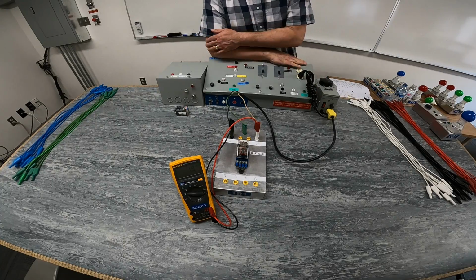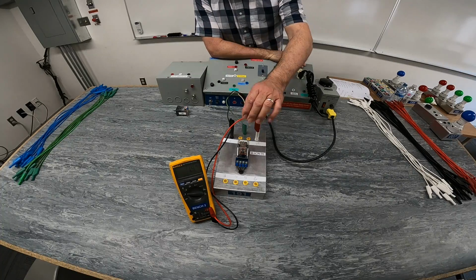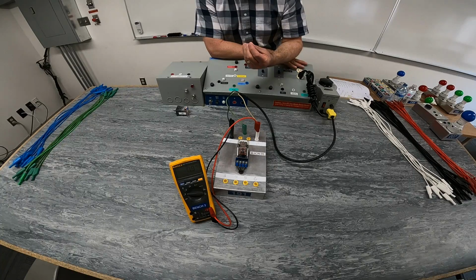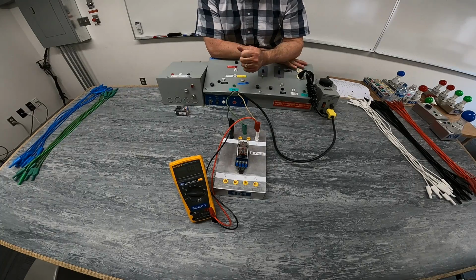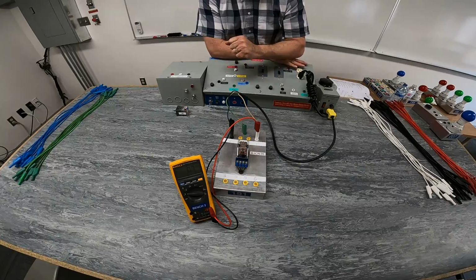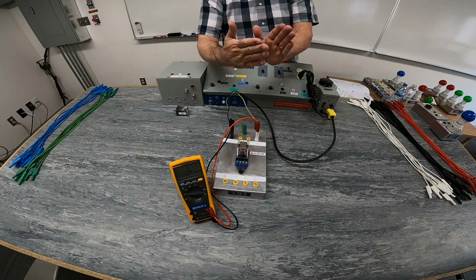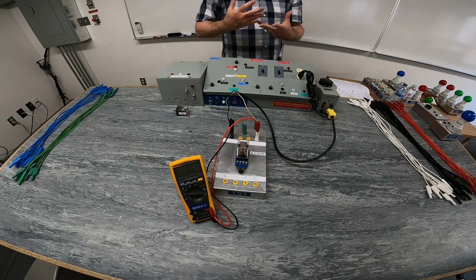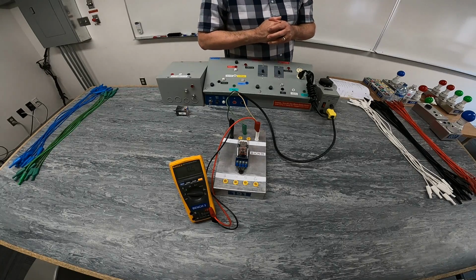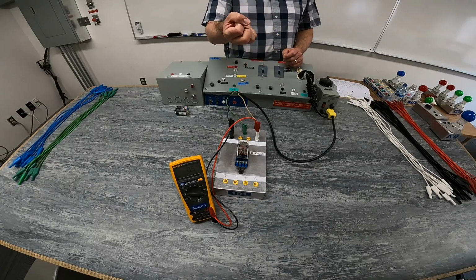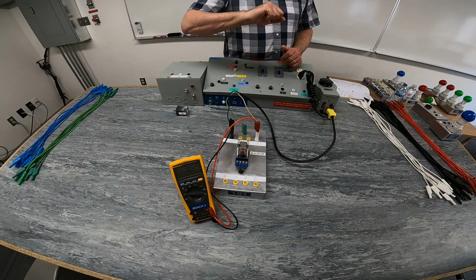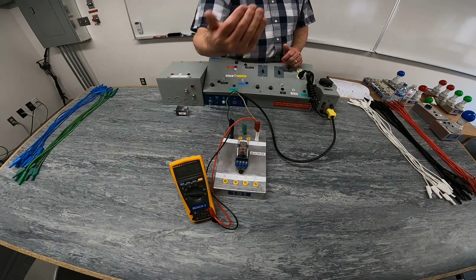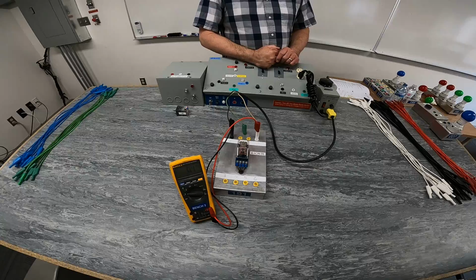So what you're going to hear is some vibrating, some buzzing sound. That's the whole process of creating enough magnetism to try to pull the armature in, and the armature is trying to get pulled into the core portion of the coil, and at one point the vibration will stop, and basically now there's enough magnetism and it just pulled the armature into the coil.